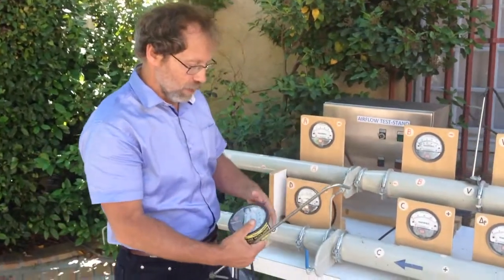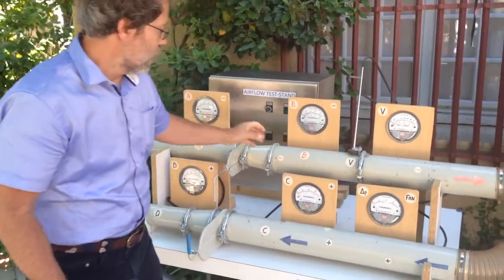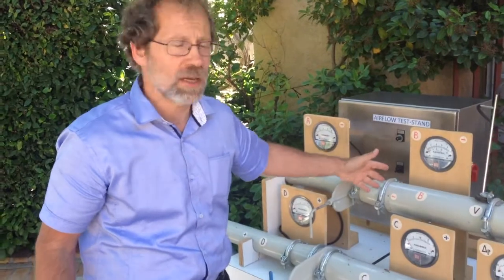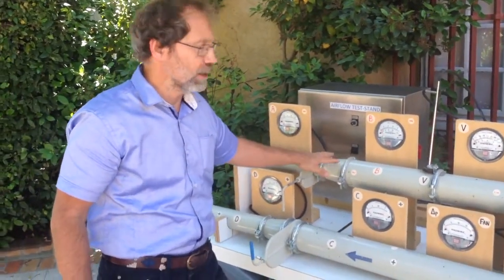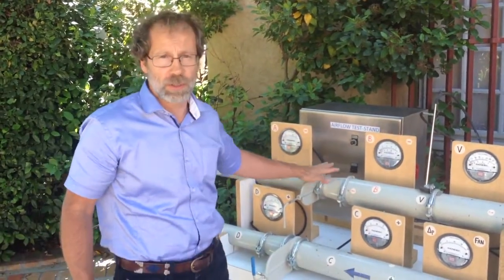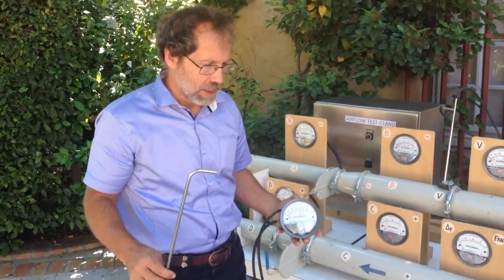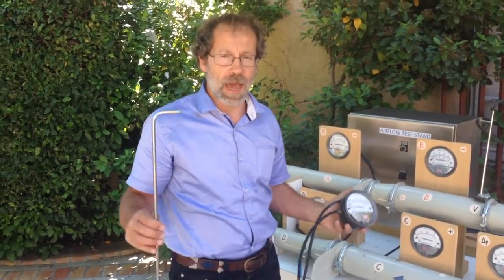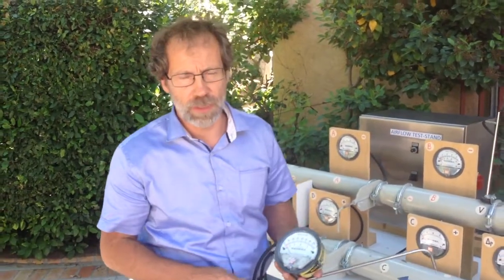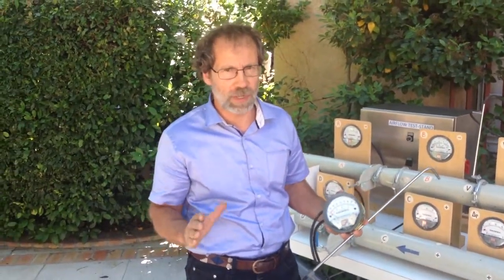I can also identify if I go with my static pressure measurement tool along the duct system. If I have an abnormal jump in the static pressure, that means I should dig deeper, and I will then find any kind of leakages or blockages in the system. And when you start doing these things, it is a little bit like you would use a voltmeter and an ampere meter to troubleshoot an electrical system, a circuit. You can do magic things with these simple tools. You can troubleshoot any kind of system.